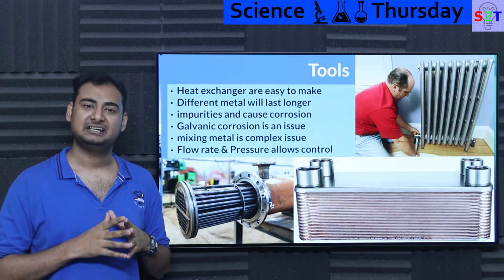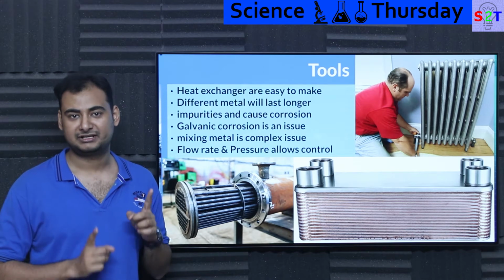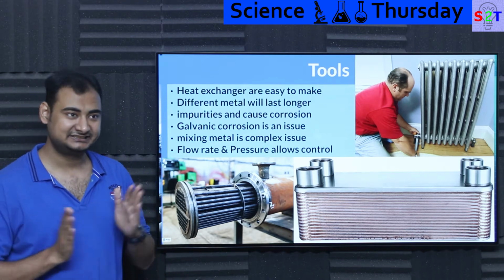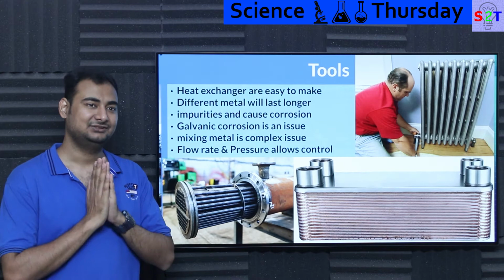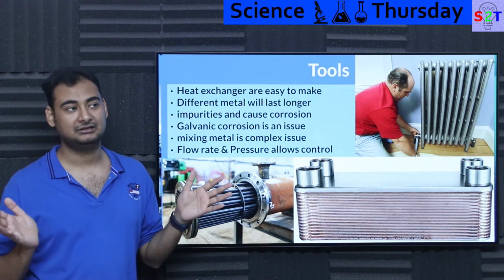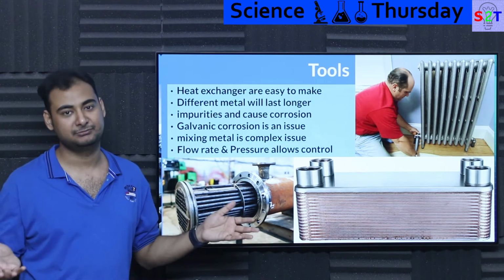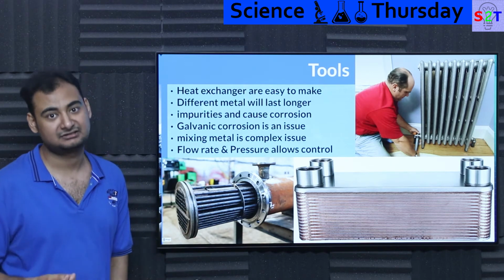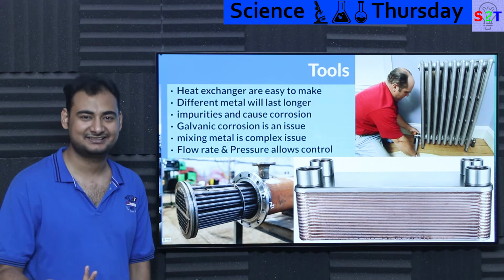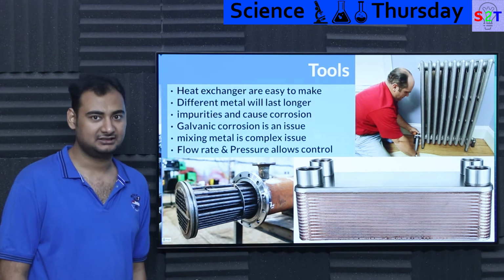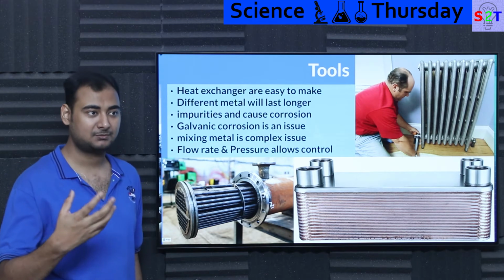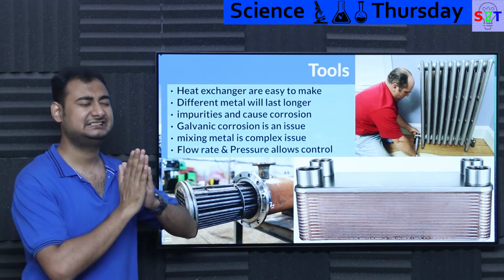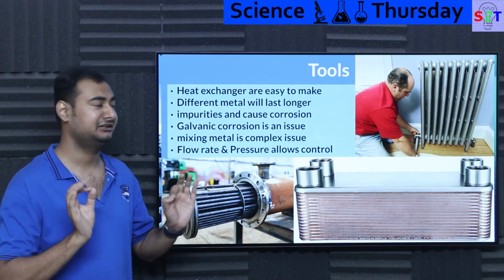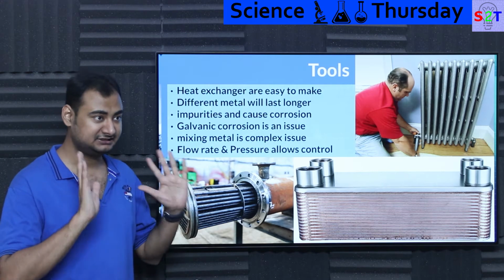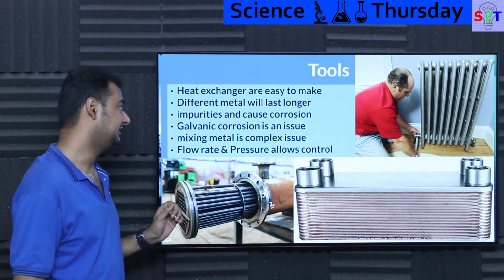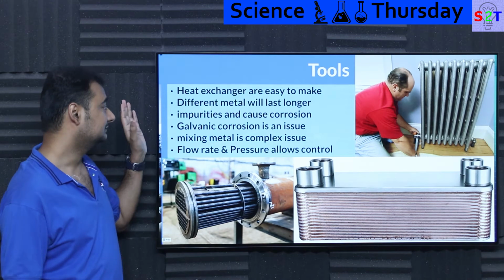Now you're like, wait a minute, isn't water conductive? Well, technically no, water is not conductive - if you have distilled water, it's surprisingly good insulator. You need to add impurities, and generally most water we see around us has impurities. For that reason, we treat water as a conductor as a safety precaution, because you can't take the risk thinking it may be distilled water. Generally it's not. That's why power plant cooling relies on water being distilled - clean AF, no particulates, no salts, nothing. It has to be distilled AF. If it's not, shock.